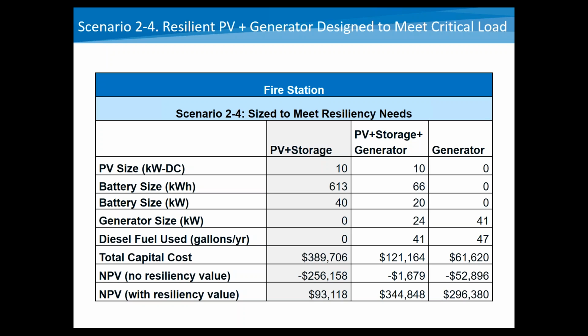This was one of our key findings across all the sites, that in general, this hybrid system of pairing PV and storage with a generator was typically the most cost-effective, because the PV and storage could provide economic savings while grid-connected, and they could provide a little bit of help and a little bit of resiliency during outages, but that generator could really provide a lot of that additional resiliency needed during outages. For comparison, we show the generator-only scenario on the right, and here you see that if you have only a generator, you need a larger generator to sustain that outage. It uses more fuel, and the NPV of the system over the 25 years is smaller.